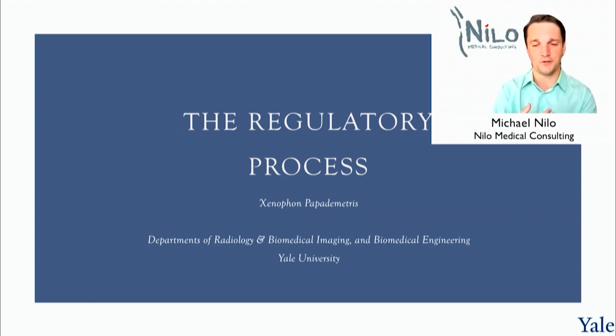The FDA won't review your code, but they will review your requirements and how you've defined your code. The other two big things for software evidence are going to be the human factors, the usability, and I mentioned that earlier, and the cybersecurity. Those three items, when most of the laws are written for a screw, like a dental implant, when you're looking at these things, a typical non-software will have mechanical testing, biocompatibility, electrical, all that stuff.